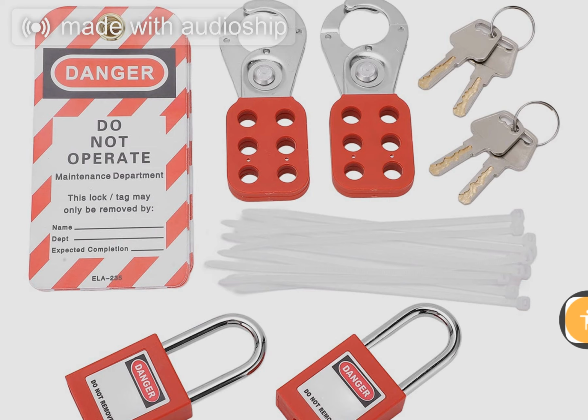Okay, step one, preparation and notification. This is where you identify every single energy source, primary, secondary, stored energy, you name it, and then you notify every single person who could be affected. Communication is the first lock. I like that. It is. Step two, shutdown. And this means using the normal operating controls, the regular stop button. You want an orderly stop, not just yanking a breaker, which could damage something. Right. So after the shutdown comes step three, isolation. This is the physical break, isn't it? This is the physical act. You open the disconnect switches, you rack out the breakers, you are creating a literal air gap where power cannot flow.